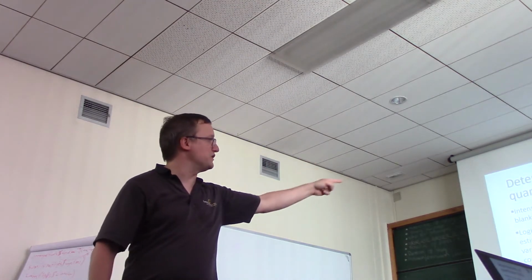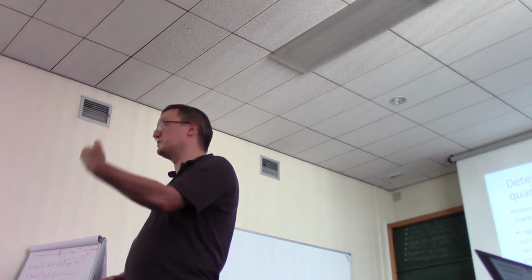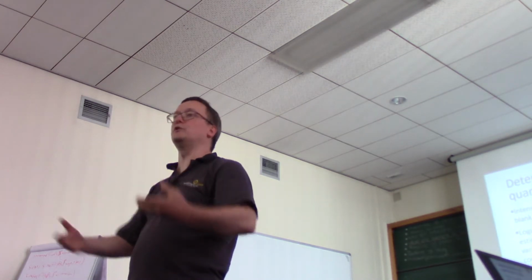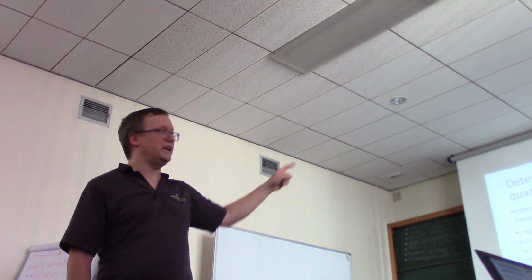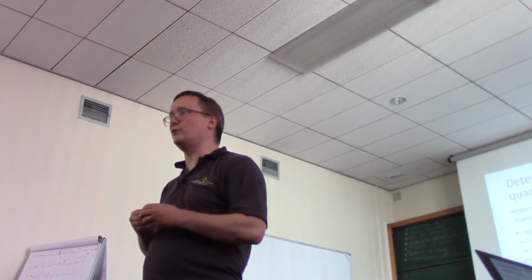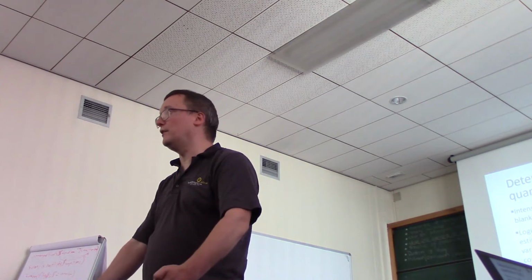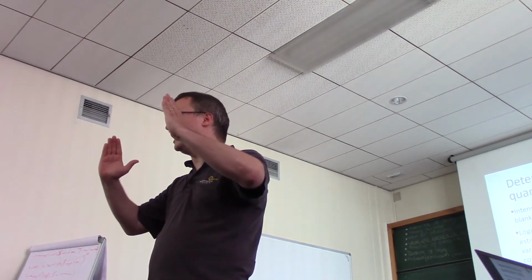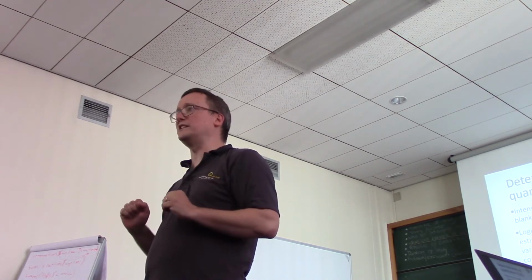So we're looking for those parts of the curve where our modeled concentration versus the true concentration is low enough in error that we feel the quantitative values have merit. Okay, that's the limit of quantitation. So you can see that this red line is the coefficient of variation at each of these points that's been estimated out of the model fit. You want that line to dip below some required level of CV, and only the concentrations that produce a coefficient of variation lower than that are considered the limits of quantitation.